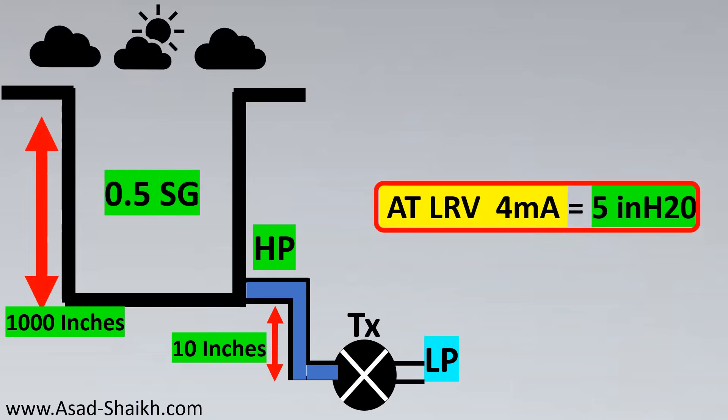You'll notice that even with no liquid in the tank, the transmitter shows 5 inches of H2O. If you had calibrated the transmitter so that 0 inches of H2O gives 4 mA, that would be an incorrect reading. When the transmitter is moved below the tapping, you must compensate for the liquid head acting on the transmitter.